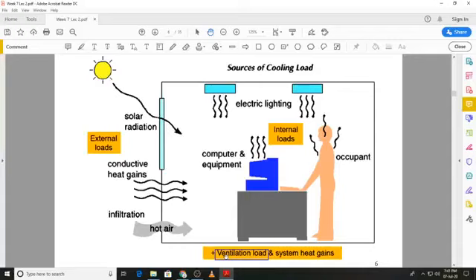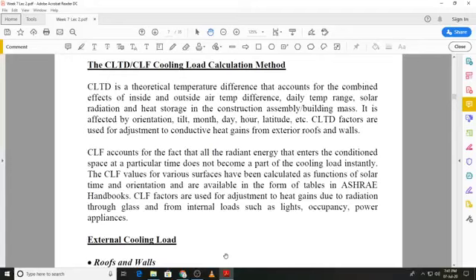But when we bring the outside air, we have to cool it to the supply conditions. That means there is an additional load on the cooling equipment. So once we have calculated the space cooling load, we also need to add the ventilation load to it, so that we can have a better idea of the total load that has to be taken up by the cooling equipment. There are various methods that have been developed over a number of years to estimate or calculate the cooling load.